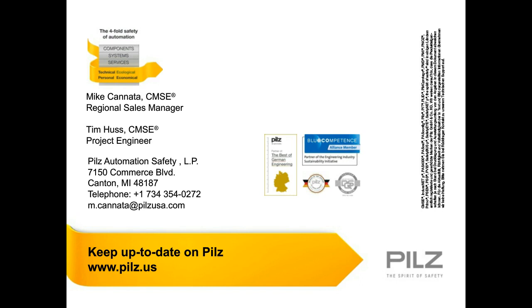Does OSHA recognize AC-23A contactors as a lockout device? There is an issue with OSHA not making up their minds and making a judgment on it. In other words, it's hard to get OSHA to change the standard. So at this point, their actual regulation or law says no. But at the same time, they accepted the UL standard into their nationally recognized testing program, and we are certified to the standard.